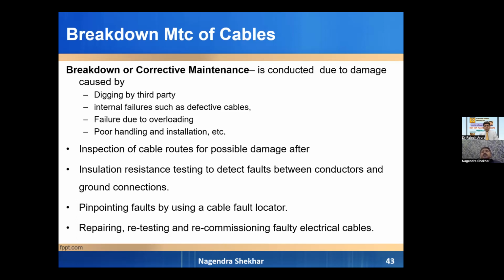The next and major reason for cable fault is failure due to overloading. In case of transfer of load or backfeeding load from one cable to another, or one circuit to another, we do not check how much load is going to occur in the cable where we are backfeeding the load. So in that condition, cables are overloaded, and above all, there is poor planning. It is assumed, as a thumb rule, that for every 125 kVA we require one LT feeder of 3 into 300 mm square. But specifically in state distribution utilities or electricity boards, I have seen 1 or 2 feeders commencing from a 630 or 400 kVA transformer. In such conditions, cables are overloaded. That is one of the major reasons.